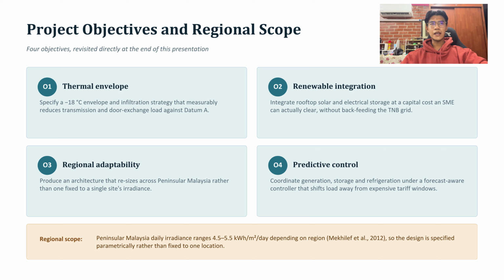Objective 3, make sure the design works not just in one city but across different parts of Peninsular Malaysia, north and south, because sunlight levels are not the same everywhere. Objective 4, use a smart controller that can predict energy usage and shift power use away from the expensive time of the day. So, this is not designed only for one location. Solar radiation in Peninsular Malaysia ranges from about 4.5 to 5.5 kilowatt hours per square meter per day, depending on the region. So, we built our sizing method to adjust to that instead of locking it into one number. Now, Ishraf will explain how we benchmark our design against the best cold storage system in the world.